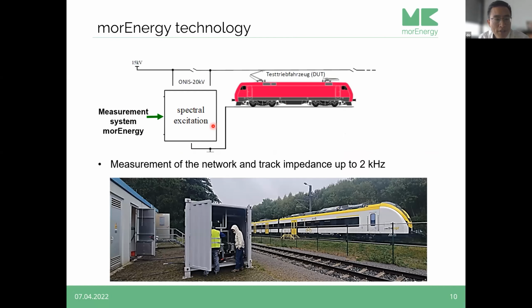So you can see here, this is our measurement system with spectral excitation. Our container is connected on the left side with the grid, and on the right side with the device under test, or the traction unit. We measure on the left side voltage and current, and also on the right side. By that way, we can get both pieces of information of the system: the grid impedance and the electrical system impedance.